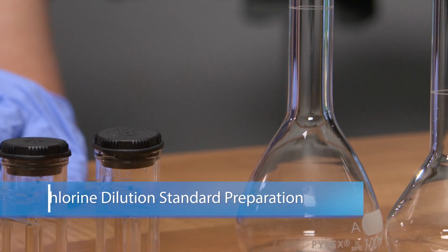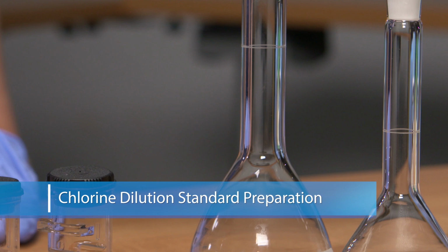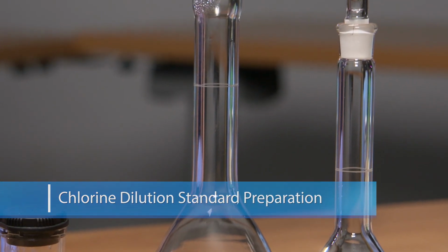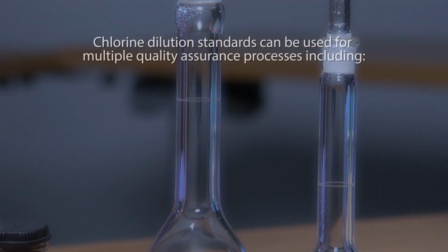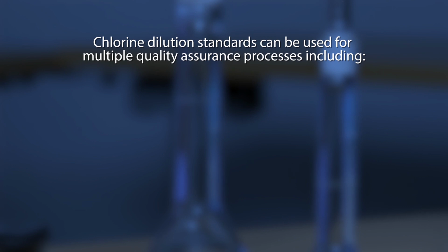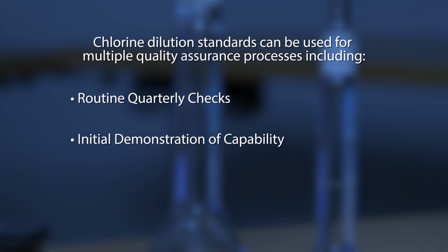Now that we've looked over our equipment and prepared our glassware, let's prepare standards that will be used for equipment calibration verification. Chlorine dilution standards can be used for multiple quality assurance processes, including routine quarterly checks, initial demonstration of capability, and initial instrument verification. First, we will learn how to prepare a chlorine dilution standard, and then we will learn how to decide what concentration is needed for the test we are performing.